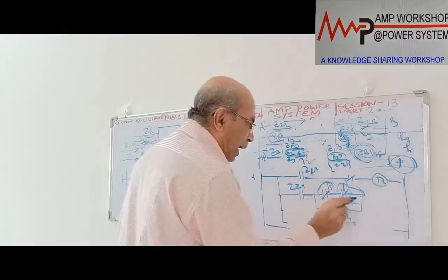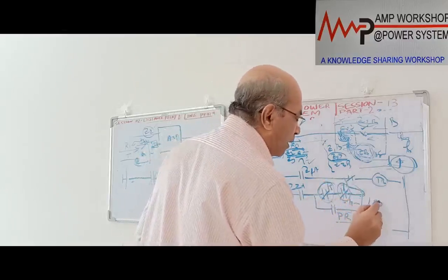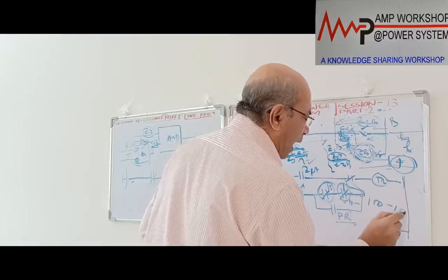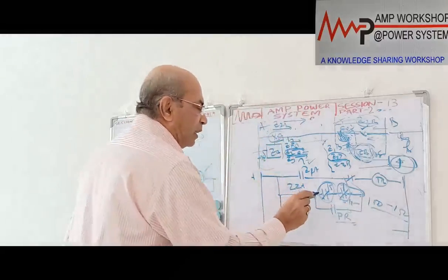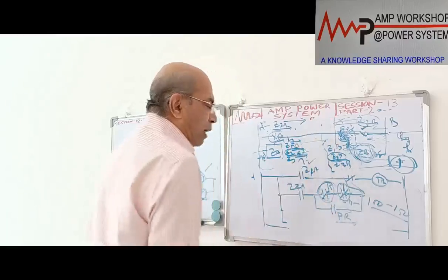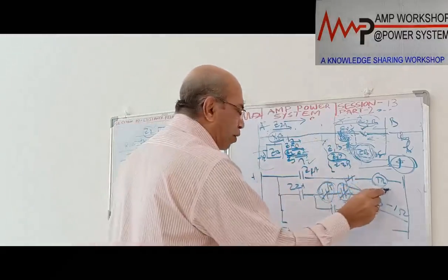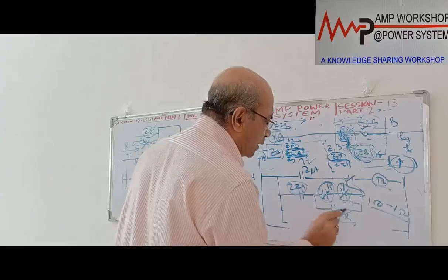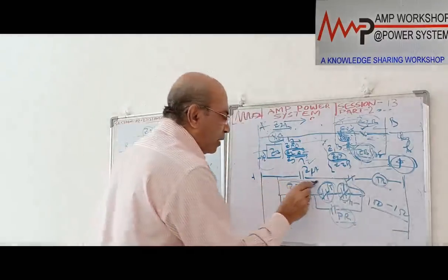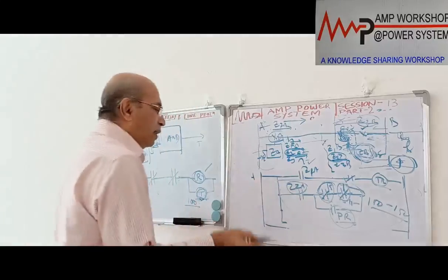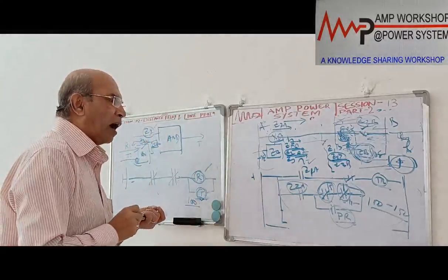So this will allow tripping for up to 100 to 150 milliseconds as per the setting of the timer. After 150 milliseconds, this path will be open, so it will not allow. At that time, if you want to trip the breaker for an end zone fault, Zone 2 has to operate and the signal has to be received. This modification we do in the circuit, and then this scheme is called the directional unblocking scheme.